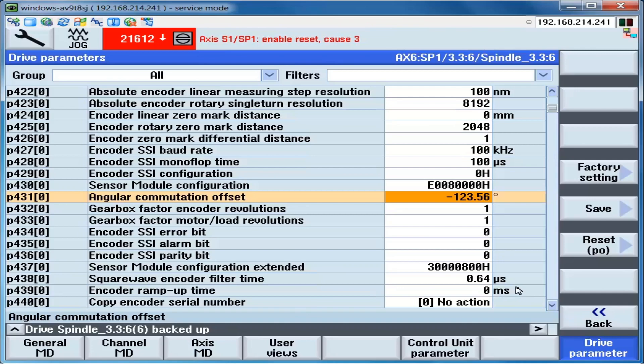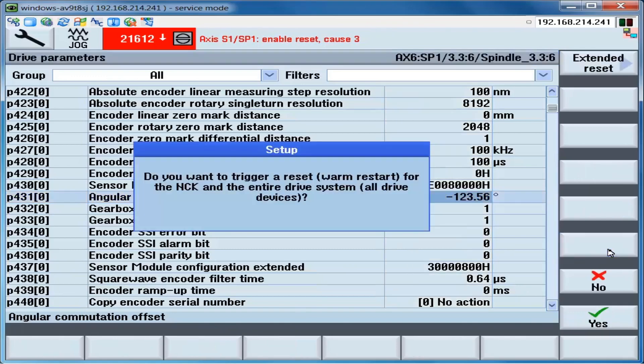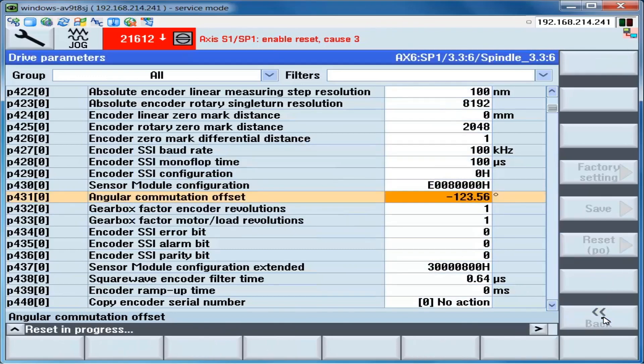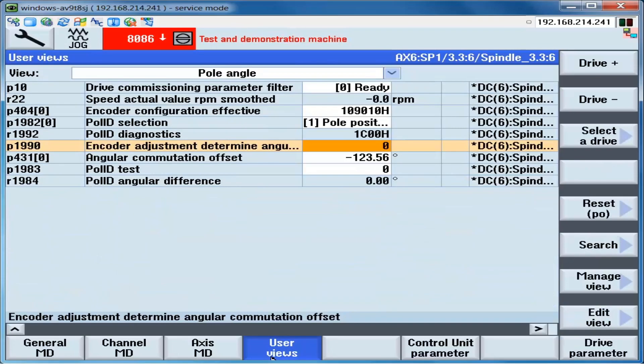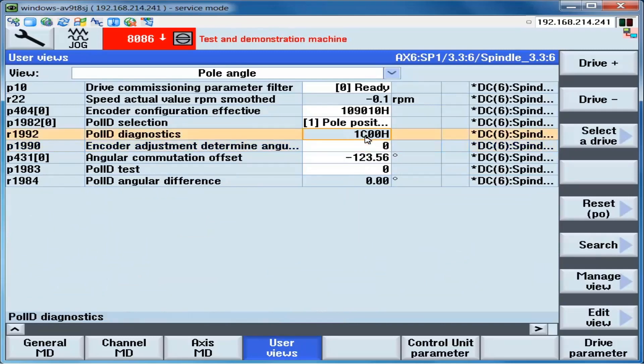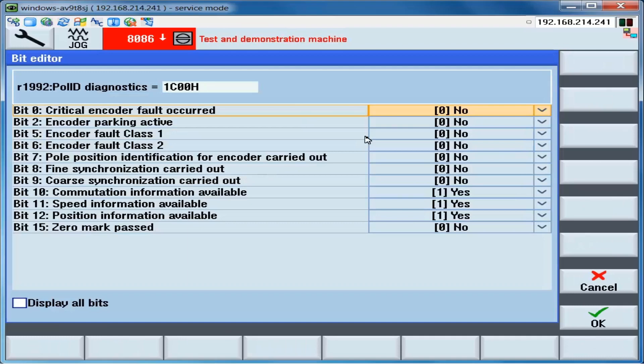Be sure that the drive is disabled. And perform an NCK reset. After the NCK reset has been completed, we go back to user views. And we can see the pole ID diagnostics shows that the coarse synchronization has not yet been carried out. This is because the drive is not enabled.